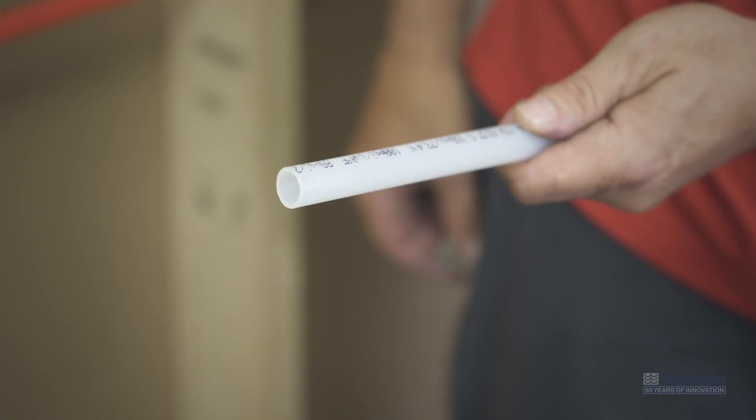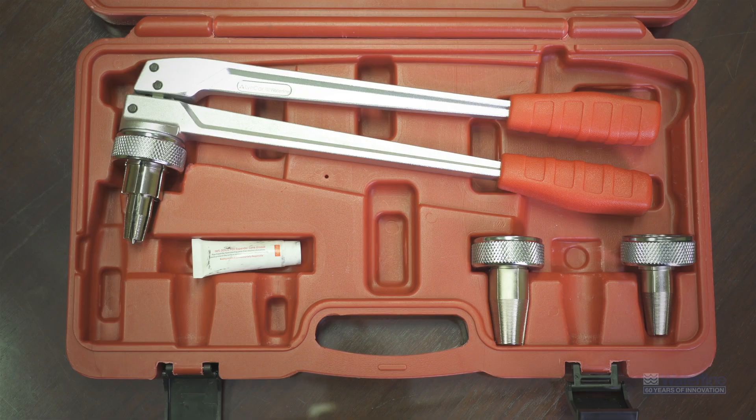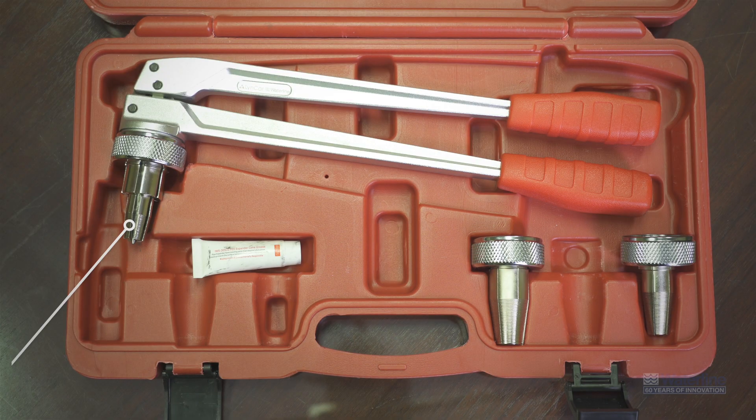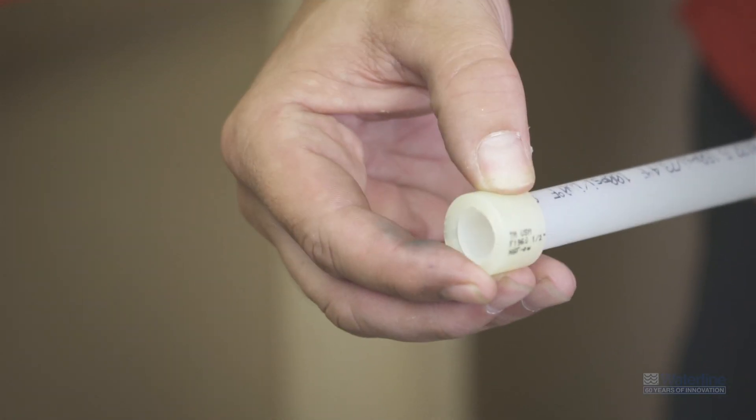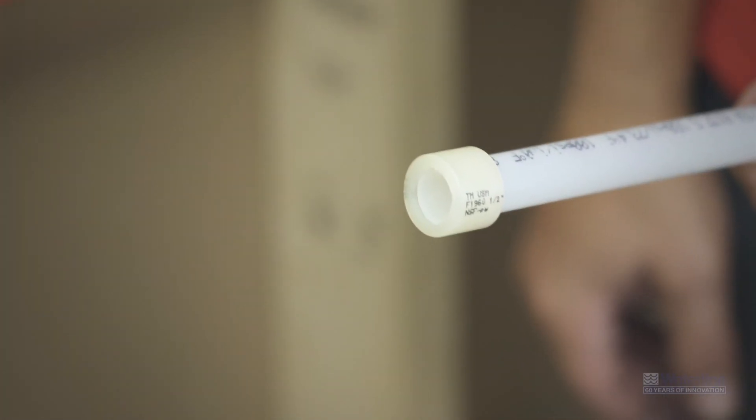Now that you've got everything, let's begin. First make sure that you lightly grease the cone of the expansion tool in order to ensure a smooth expansion. Then place a ColdX expansion ring onto the pipe as far as you can. There's a built-in stop on the ring so that you will know that it's in its place.